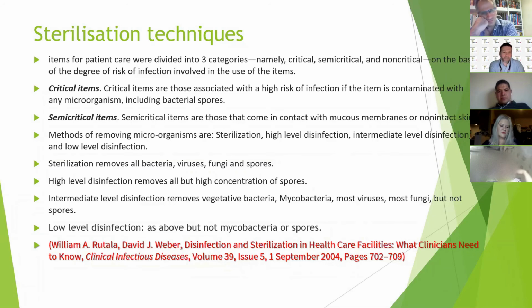So you have cleaning, which is just removal of the dirt, but not specifically removal of bacteria. You have sterilization, high-level disinfection, intermediate-level disinfection, and low-level disinfection. And you will be expected to know the difference between them. Basically, sterilization is when you remove all bacteria, viruses, fungi, and more importantly, spores. The high-level disinfection, you remove everything but spores. The low-level disinfection, everything but you don't remove mycobacteria or spores. Okay, all of them are disinfection. Cleaning doesn't remove any of these. It's just visible dirt.